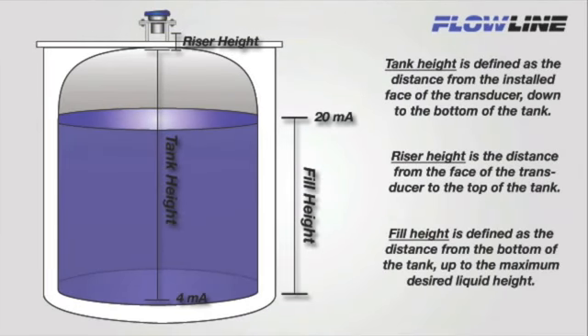Now, let's talk about tank height, fill height, and riser height. Tank height is defined as the distance from the installed face of the transducer down to the bottom of the tank. This is where the 4 milliamp set point will be placed. 4 milliamps will then equal tank empty. Fill height is defined as the distance from the bottom of the tank up to the maximum desired liquid height within the tank. This is where the 20 milliamp set point will be placed. 20 milliamps then equals tank full.